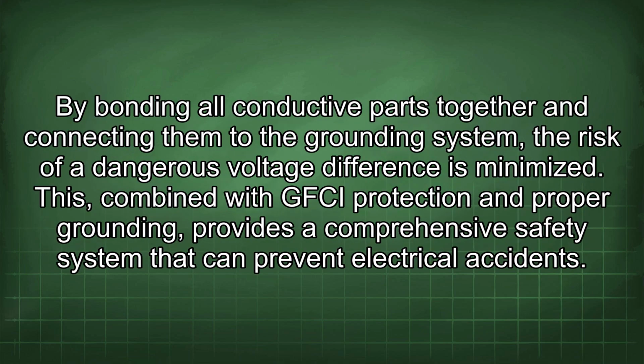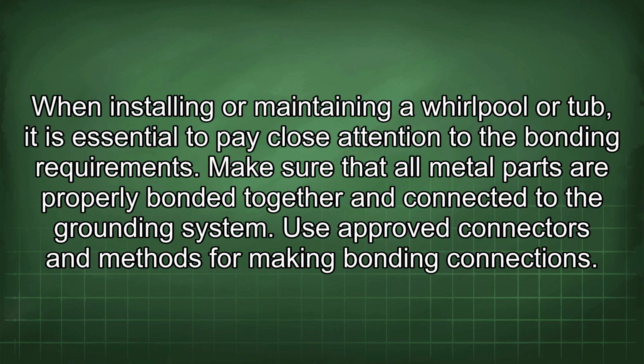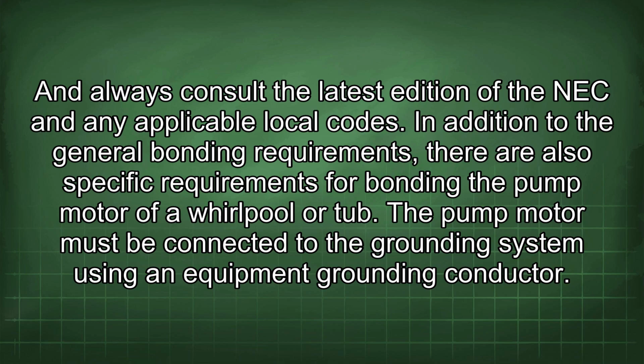By bonding all conductive parts together and connecting them to the grounding system, the risk of a dangerous voltage difference is minimized. This, combined with GFCI protection and proper grounding, provides a comprehensive safety system that can prevent electrical accidents. When installing or maintaining a whirlpool or tub, it is essential to pay close attention to the bonding requirements. Make sure that all metal parts are properly bonded together and connected to the grounding system. Use approved connectors and methods for making bonding connections. And always consult the latest edition of the NEC and any applicable local codes.